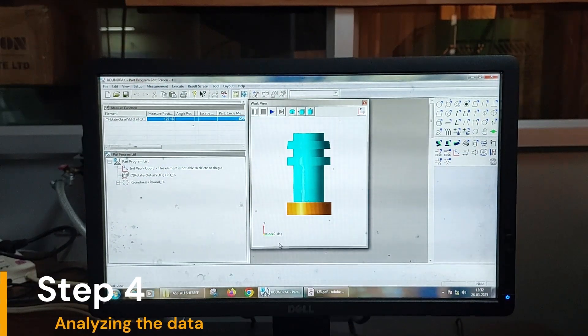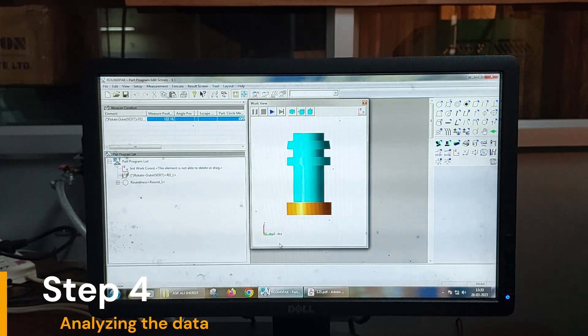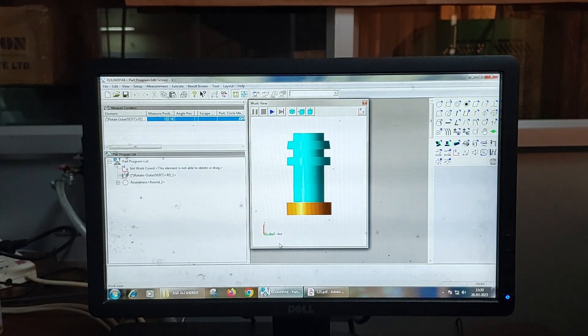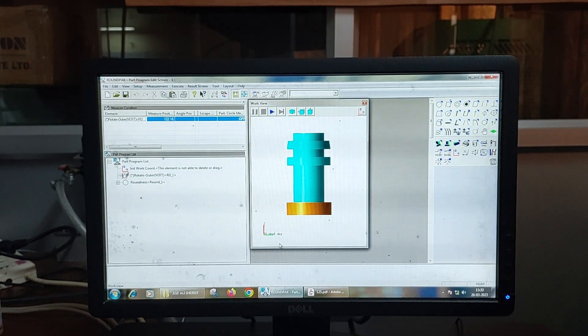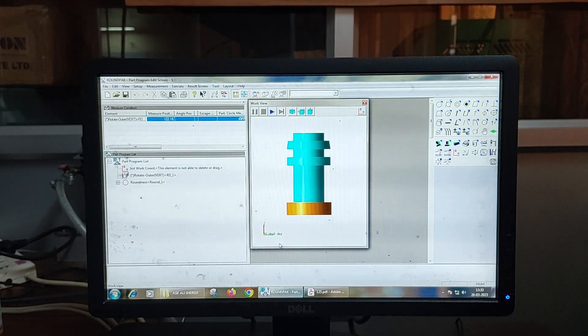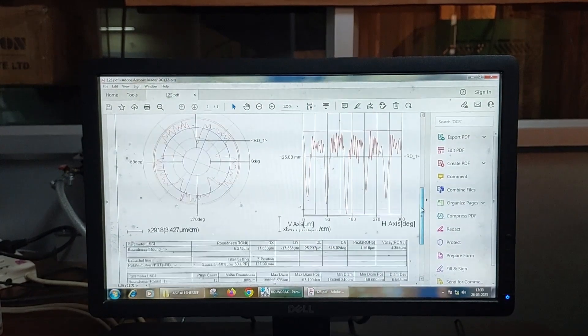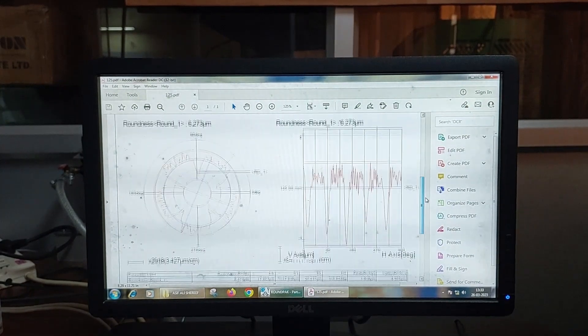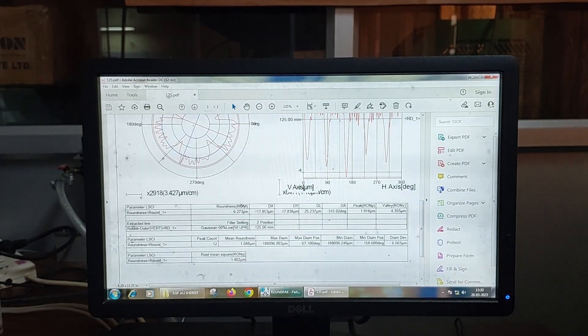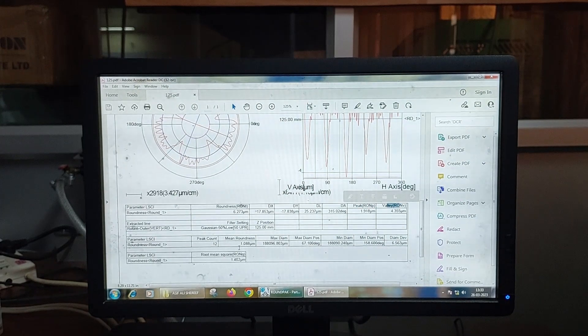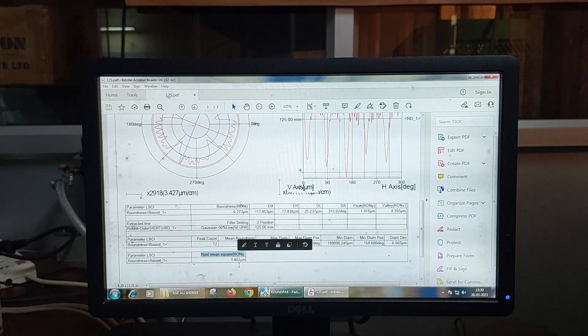The fourth step is Analyzing the data. After the measurement process is complete, the data collected by the instrument needs to be analyzed to determine the roundness of the specimen. The Mitutoyo RA-1600 software can perform this analysis automatically and generates a report that includes measurements such as RONT, RONP, RONV, mean roundness, and root mean square roundness.